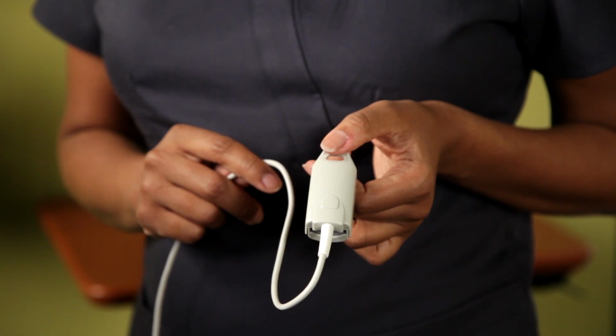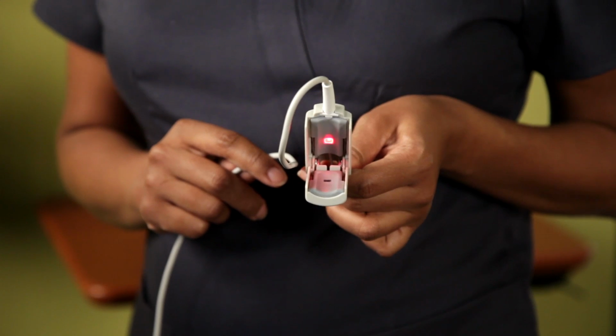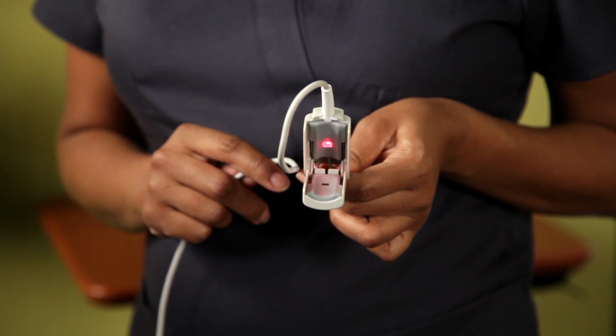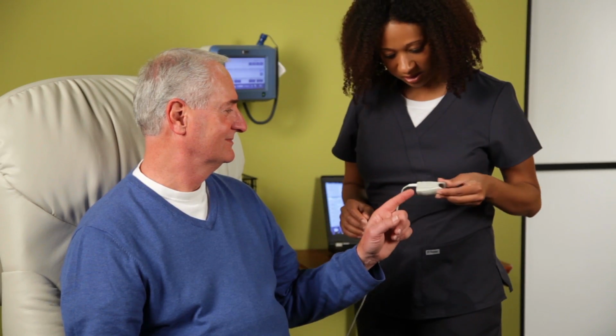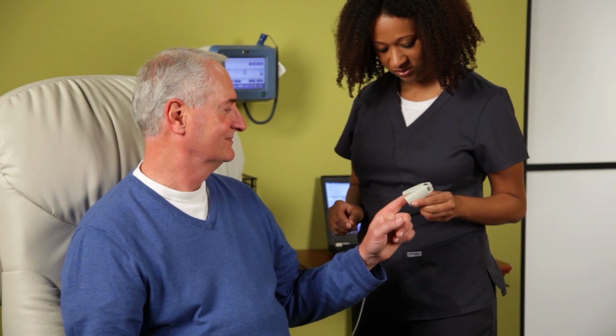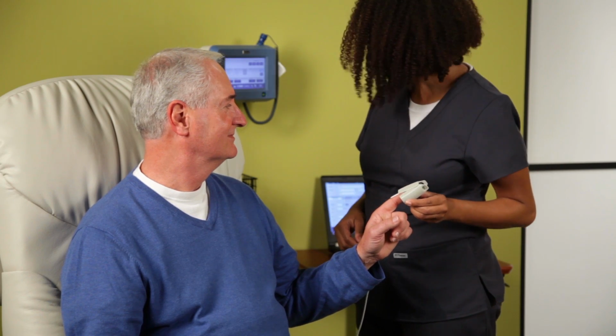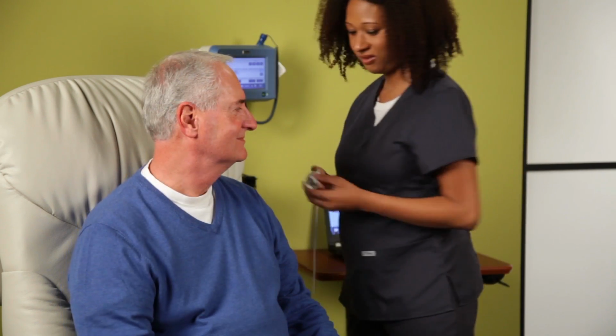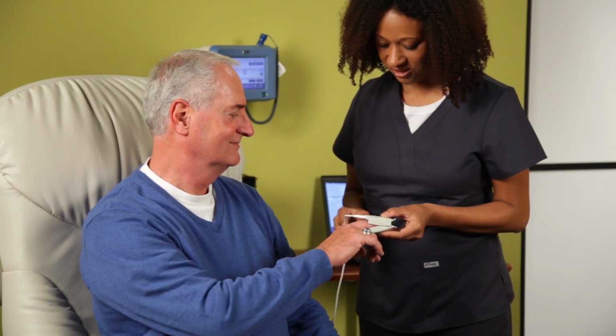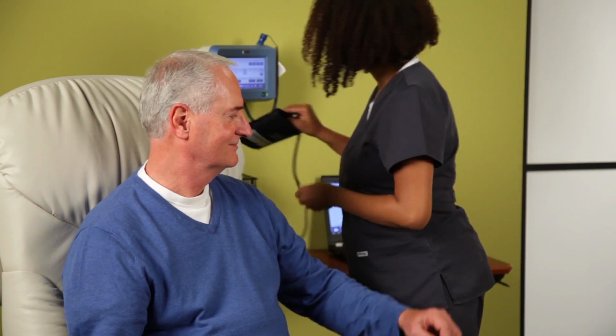To perform an SpO2 measurement, place the sensor with the LED light positioned at the fingernail. Insert the patient's finger, using the left or right index finger, completely into the sensor. If a blood pressure measurement is occurring simultaneously, place the finger clip sensor on the limb opposite the one with the blood pressure cuff.